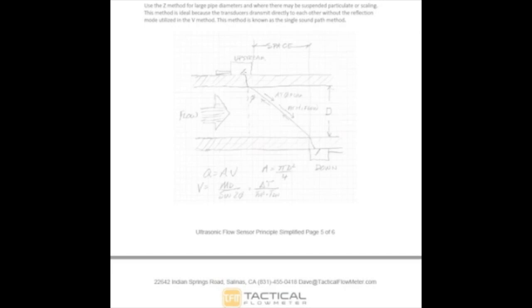So what we're doing is we're measuring the time of flight, the time of flight from this transducer to that transducer through this medium. This could be a pipe, could be cast iron, could be rubber, could be plastic, could have a liner. As the acoustic pulse travels through this metal, it's going to go faster in the metal than it will through air.